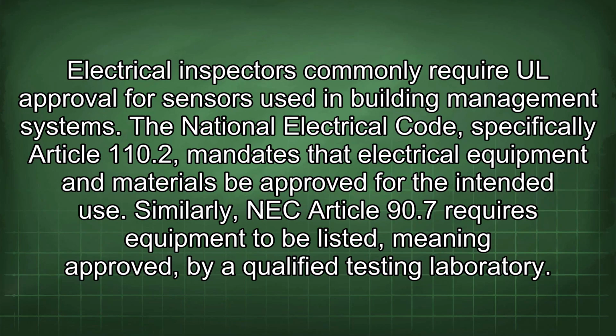Electrical inspectors commonly require UL approval for sensors used in building management systems. The National Electrical Code, specifically Article 110.2, mandates that electrical equipment and materials be approved for the intended use. Similarly, NEC Article 90.7 requires equipment to be listed, meaning approved, by a qualified testing laboratory.